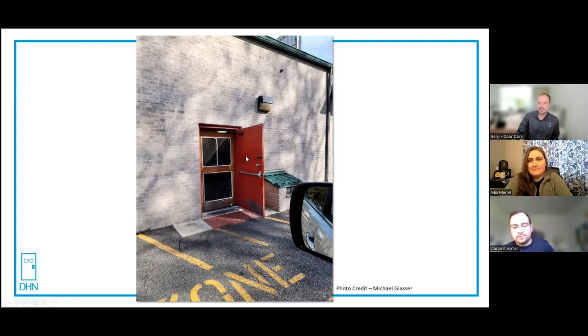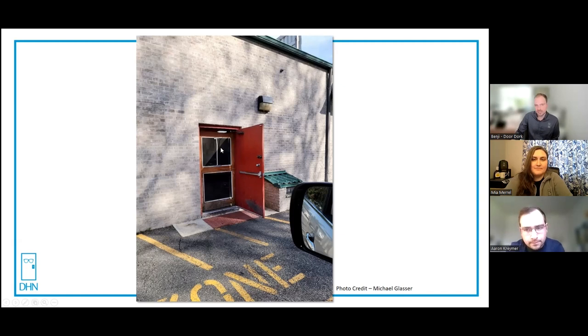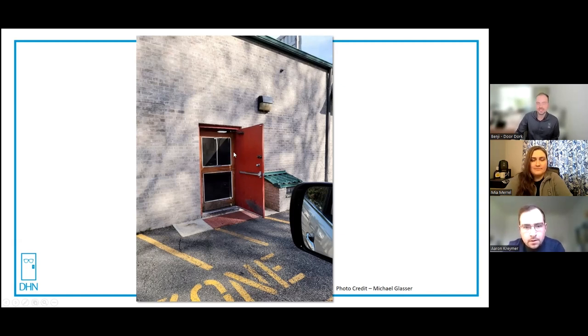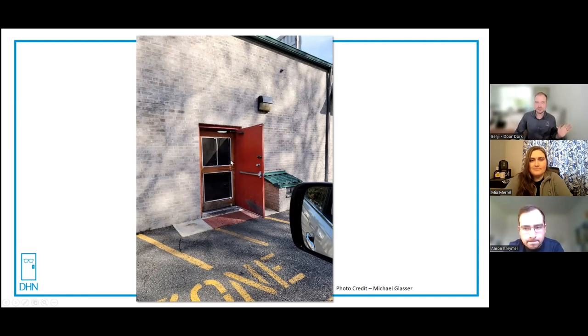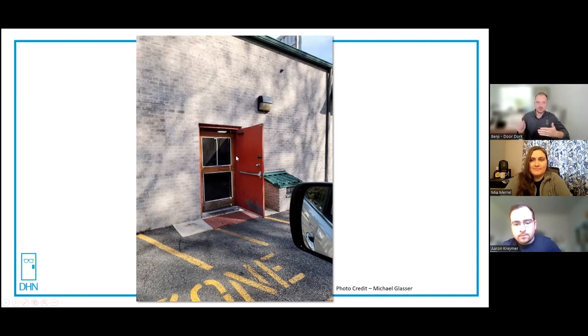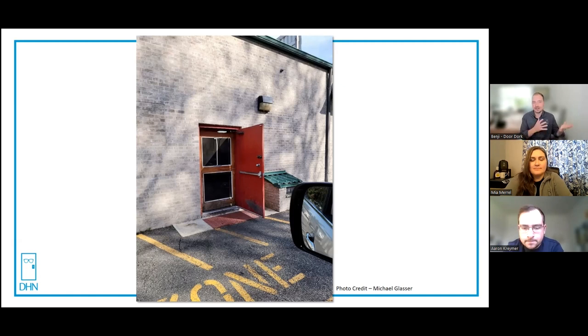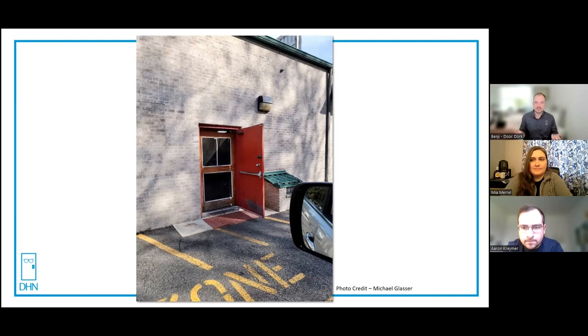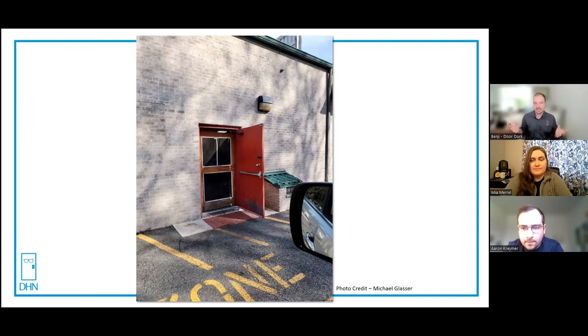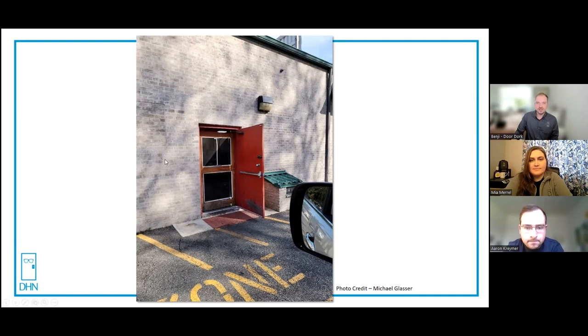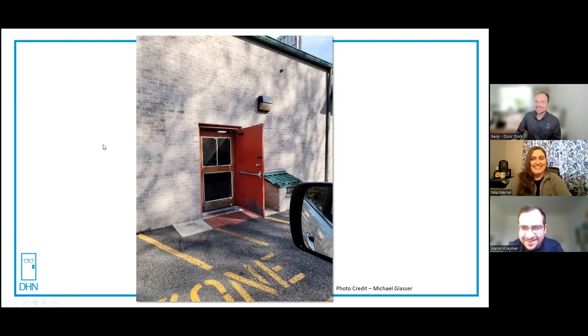Because if it is bolted during operation, which I doubt it is, that's probably end of the night closing, but there could be some life safety issues here. And especially having a barrier in between egress with the screen door is bad. I agree. I would say, even if they are unbolting this during the day, that they would need a sign. Code requires a sign on here saying that this needs to remain unlocked during business hours or occupation or something like that. By itself right now, and probably their typical use, it's not that big of a concern. But if worst case scenario, they had that door behind it bolted, they could be really bad in the case of someone breaking in the front door. I mean, this is still life safety, not just fire hazard or concern. But if someone breaks through the front door or tries to stick you up, this is your one exit out. So if it's thrown during morning hours or something like that, it could lead to some dangerous situations. Okay, the final photo. Are you guys ready? I'm still confused about this one. So let's dive in.